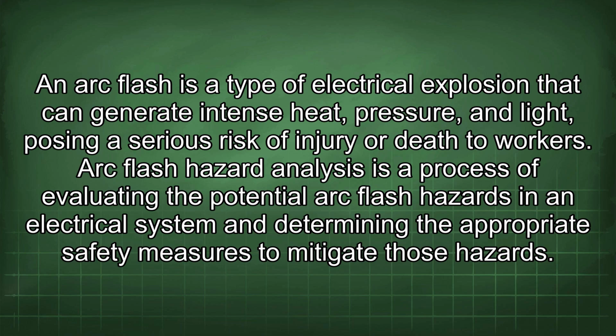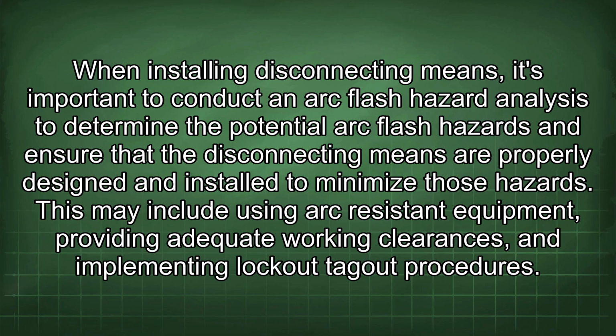Arc flash hazard analysis is a process of evaluating the potential arc flash hazards in an electrical system and determining the appropriate safety measures to mitigate those hazards. When installing disconnecting means, it's important to conduct an arc flash hazard analysis to determine the potential arc flash hazards and ensure that the disconnecting means are properly designed and installed to minimize those hazards. This may include using arc-resistant equipment, providing adequate working clearances, and implementing lockout-tagout procedures.